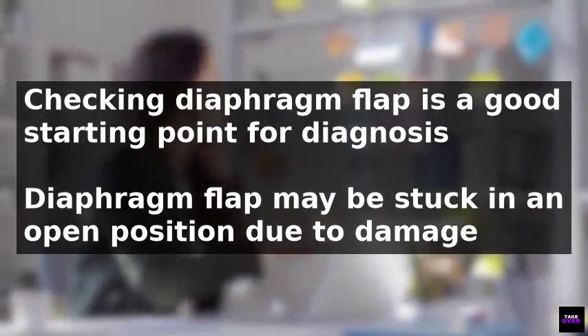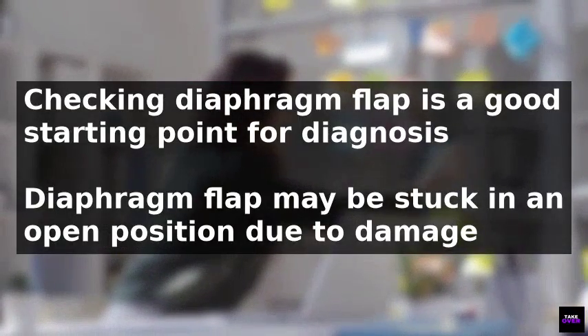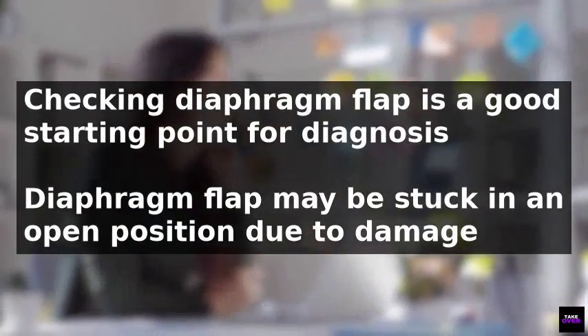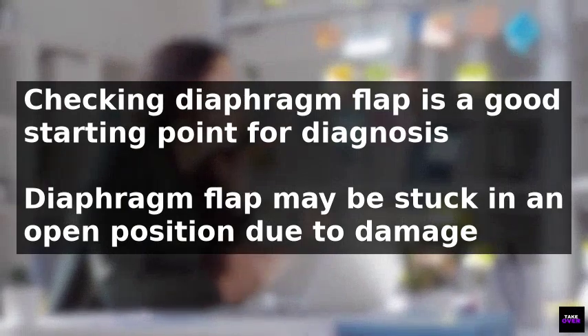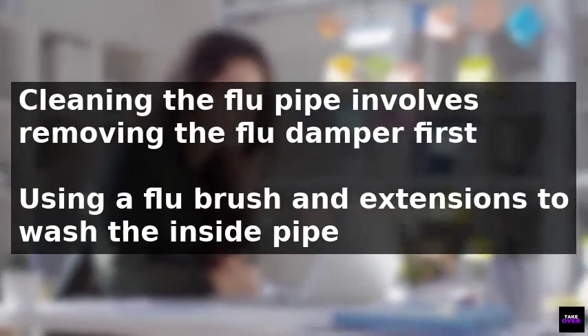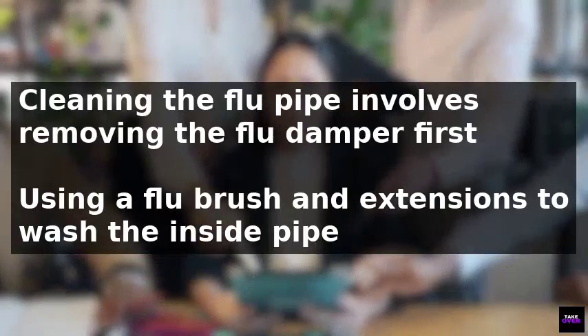Checking the diaphragm flap is a good starting point, as it may be stuck in an open position due to damage, preventing the electrical circuit from being completed when the boiler is switched on. If the diaphragm flap is found to be faulty, it should be replaced. Alternatively, the flue pipe may be clogged, preventing waste gases from escaping the system.